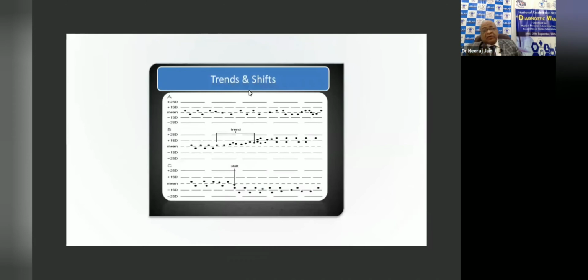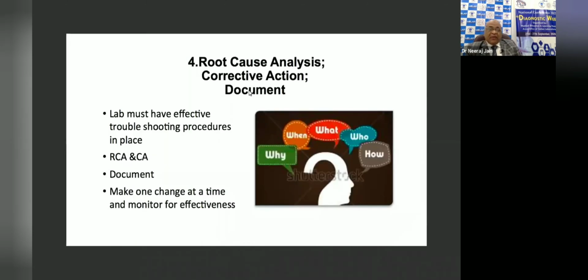Sometimes what happens, suppose you are reconstituting a new vial of control. Previously in glucose, you were getting results close to 99.6, 99.8, 99.4 like that, and suddenly now you are getting a result of 105 after reconstitution, and then 105.3, 105.4, close to 105. This is called shift. Results have shifted in one direction, and those then are maintained in that shifted position. So whatever the situation, identification and proper action is very important.